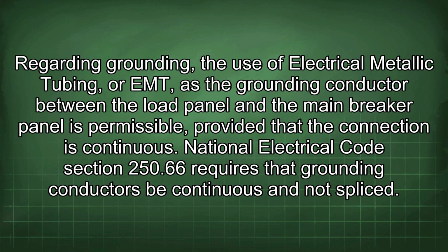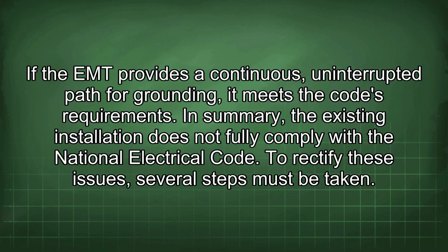Regarding grounding, the use of electrical metallic tubing, or EMT, as the grounding conductor between the load panel and the main breaker panel is permissible, provided that the connection is continuous. National Electrical Code Section 250.66 requires that grounding conductors be continuous and not spliced. If the EMT provides a continuous, uninterrupted path for grounding, it meets the code's requirements. In summary, the existing installation does not fully comply with the National Electrical Code.